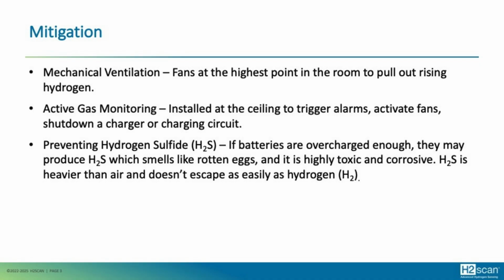It could be an audible alarm and a visual light if you want just the basic kind of system that says, I have hydrogen in the area, so it activates these alarms and alerts you to the fact that hydrogen is present. It could also be connected to the fans to activate them automatically as part of your mitigation strategy. It can also connect to the charger itself to provide charger shutdown, or shutdown of the whole charging circuit. If hydrogen were to rise above 1%, maybe it could trigger a fan. And then maybe a second alarm says, okay, this is more critical, it's rising further, and it shuts down the whole system.